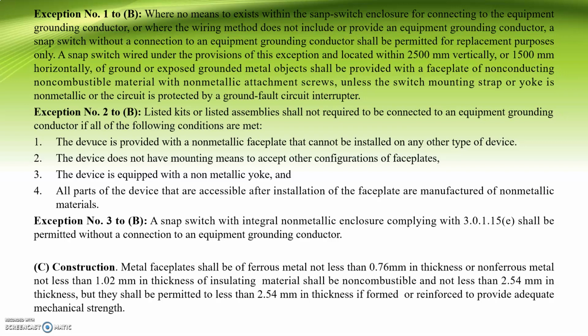So exception number 3 to B. A snap switch with an integral non-metallic enclosure complying with chapter 3.0.1.15e shall be permitted without a connection to an equipment grounding conductor. So letter C, construction.